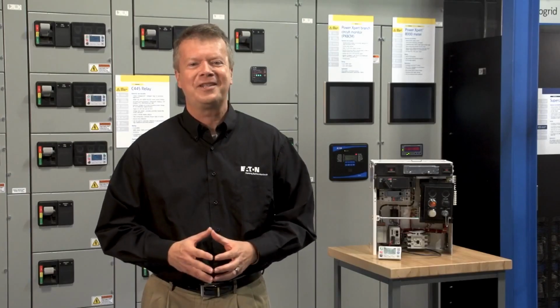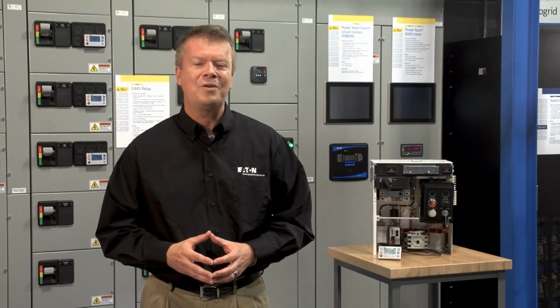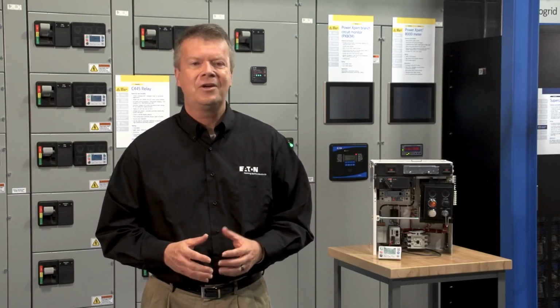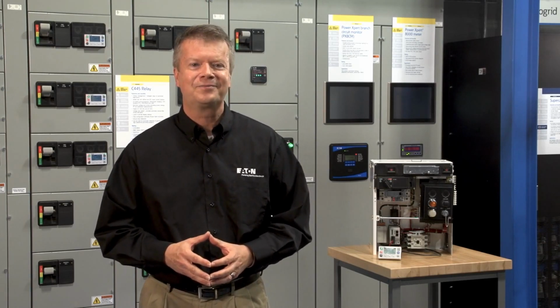Kick-out springs are used to allow the contactor to be mounted in any position. Contactors use over-travel springs to ensure that an adequate level of pressure is available when the main contacts are closed. We mentioned earlier that the life cycle of a contactor is about 1 million operations, but this is highly dependent on whether it is a latched or magnetically held contactor.